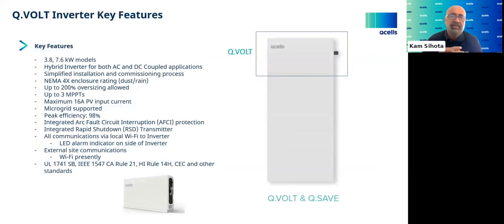This is a little deeper look at the inverter. As I said earlier, there are two inverter flavors. It's a NEMA 4X enclosure that's weatherproof, rainproof, and dustproof, allowing you to put it indoors or outside. The DC oversizing is 200%, so you can put 15.2 kilowatts DC on a 7.6 kilowatt inverter. That inverter has 3 MPPTs, so one way to manage shade mitigation or different roof angles is to put each string on a separate MPPT - a simple way to keep it simple.